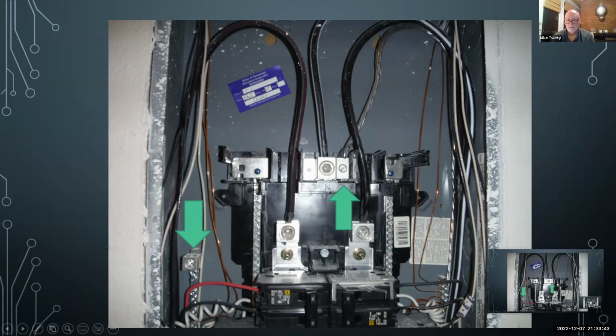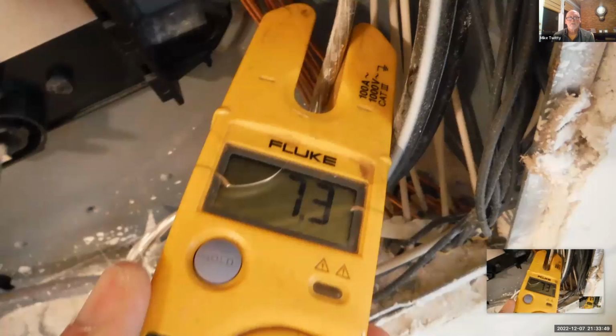See that? I took some amp readings on this particular panel with a load on it. There's 7.3 amps on that bare equipment ground feeder. It's going back from the breaker that's feeding that sub panel. Very dangerous. That same current's on that metal can. If you touch it, everything that's bonded in that system is getting that current on it.